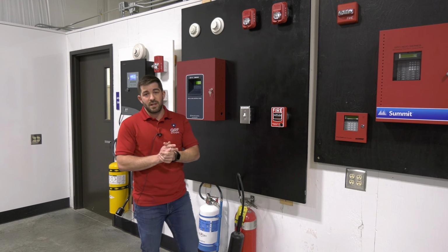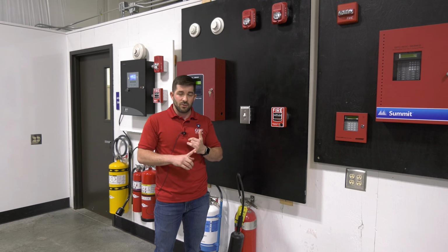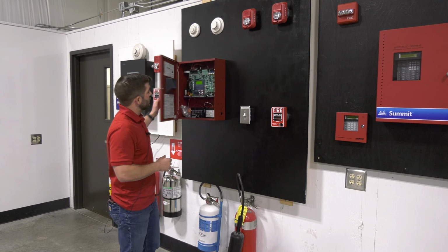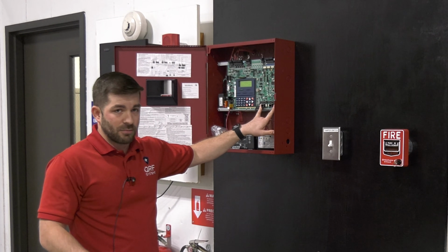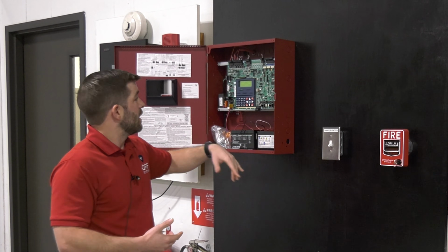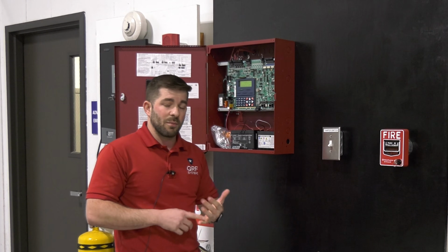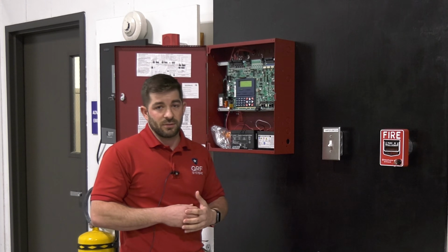Now, I'm going to go over the three most common ways that a fire alarm panel is monitored. You have your onboard DAC, which is your digital alarm communicator transmitter, and you have cellular, and you have IP. Now, most panels today have an onboard DAC. Your onboard DAC is your phone lines, either copper or you can use a cellular communicator, which is in place of those copper phone lines. And whenever you program, you put in your 4 to 6 digit account number, and you have to put in a primary and secondary receiver number. That's telling this panel where to transmit signals to.